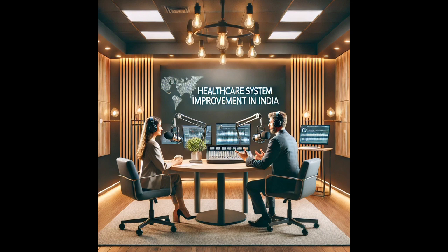Exactly. Now, the FDA talks about specific records, like the design history file, DHF. What's the core idea there? Right, the DHF. It basically tells the story of how a finished medical device was designed. It's a compilation of records tracing its whole design history, its evolution. So the why and how it came to be. Kind of, yeah. More the how of the design process itself. And it's critical. Missing pieces there could cause serious problems later. Recalls, patient risk. Okay.